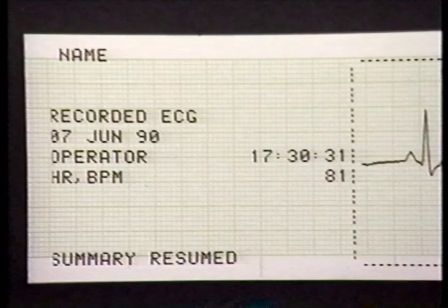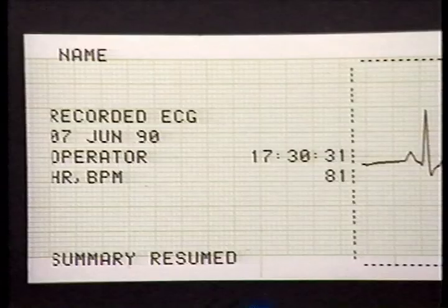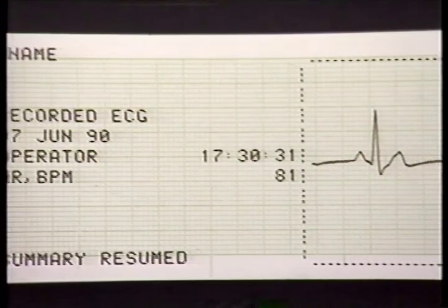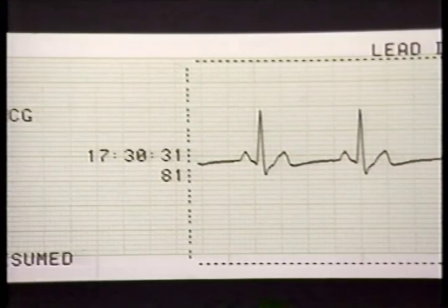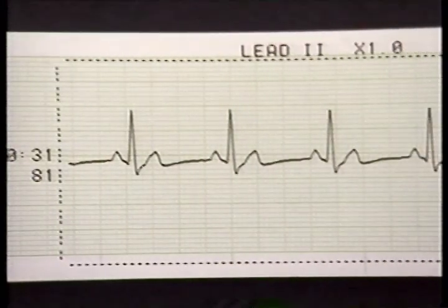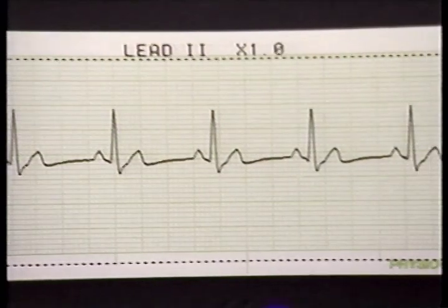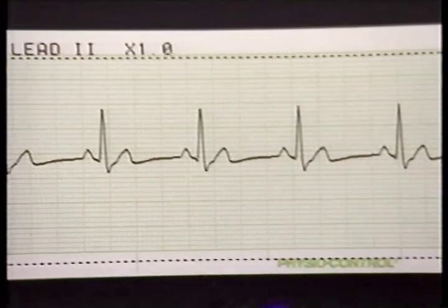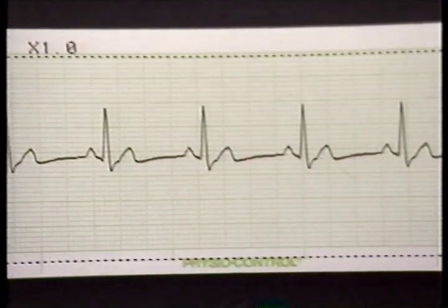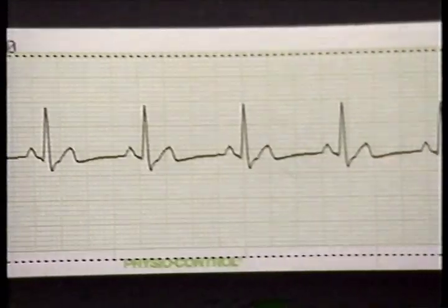The Code Summary critical event record will be interrupted whenever the recording mode is activated, the batteries are switched, or the defibrillator is charged. If it's interrupted, it will continue to store information, and when it's reactivated, it will print Summary Resumed and reprint the last segment and all other information it has stored. If Code Summary's memory capacity is exceeded, information is prioritized, first by defibrillation, next by pacing, and then by recorded ECG.